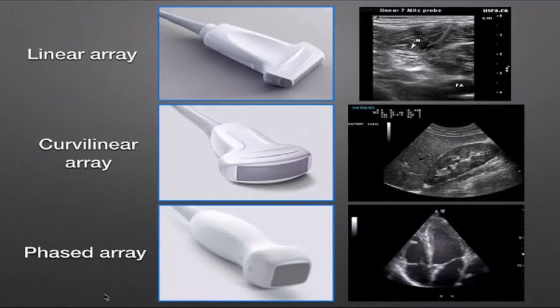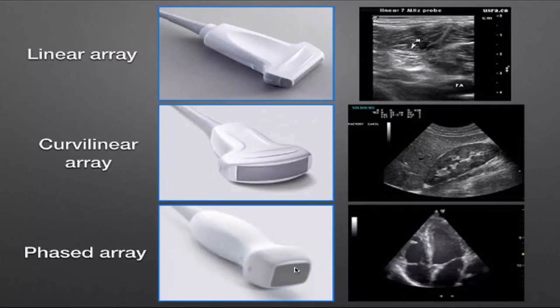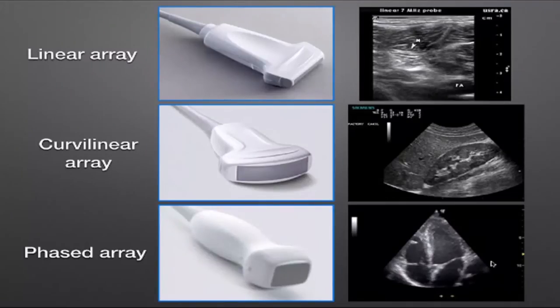The phased array probe — discussed extensively in this lecture series — sends out a wedge-shaped beam from a single point with a narrow footplate of about 1–2 cm by 1–2 cm. This allows it to sit in the intercostal space very nicely. Using electronic phased delays to steer the ultrasound waves in different directions, it can image as much of the heart as possible while keeping the probe in one position.